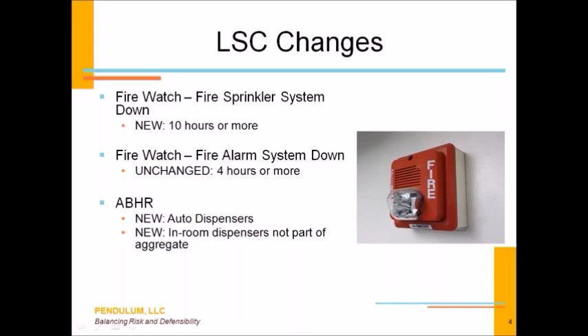Now, I'm going to take off the regulator's hat for a second and go back to the firefighter, or the administrator, or even the maintenance director's perspective. If your fire suppression system goes down at any time, you're not going to wait for 10 hours to initiate a fire watch. You're going to likely initiate that fire watch immediately because you know that your fire suppression system is compromised, or even your fire alarm system. You would go into a fire watch immediately. The key element when it comes to compliance is that you don't need to go into a formal and documented fire watch until that suppression system is down for 10 hours or more. And within your policies and procedures for fire watch, you likely have some obligation to notify the local authority having jurisdiction, meaning the fire department, and to call your state regulatory body and let them know that your system is down.